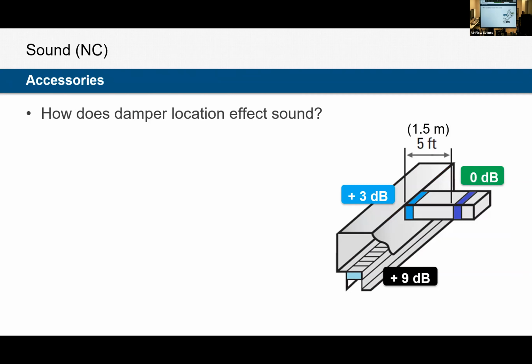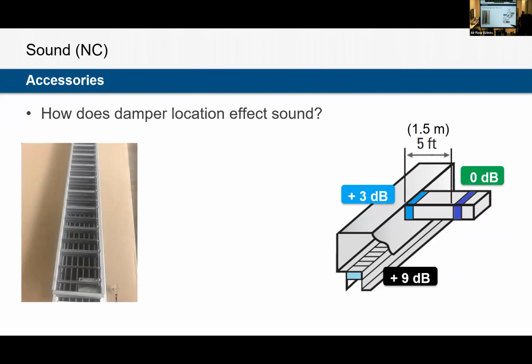And then my final point here: dampers and how they affect sound out of a diffuser. All the catalog performance is just a straight diffuser, no damper on it. But often we have to add dampers in the field. The rule of thumb is to put the damper as far away from the air outlet as you can. If you put a damper right at the air outlet, as shown here on the back of that register, you are changing the velocity of the air right at the outlet, where the occupant can hear it the most, so you're going to see the biggest increase in sound. As we move that damper further upstream, we can cut that sound generation down to nothing if we get it out of the actual diffuser itself.